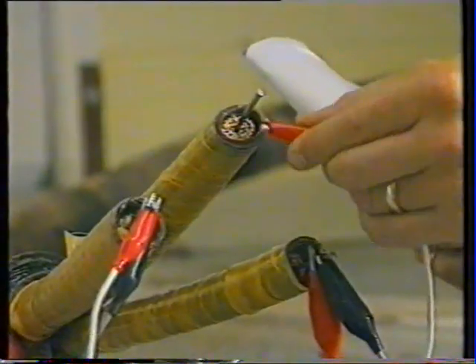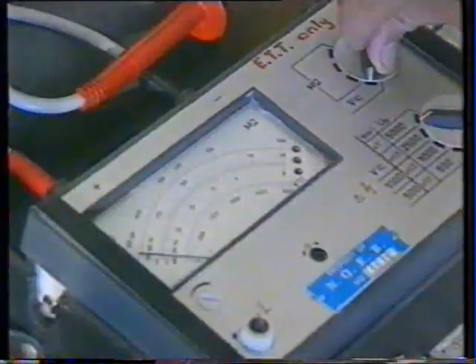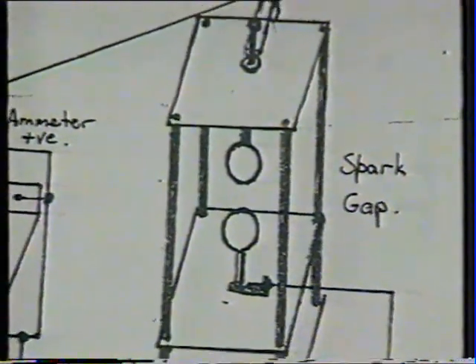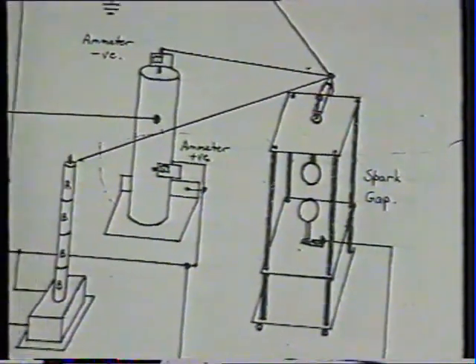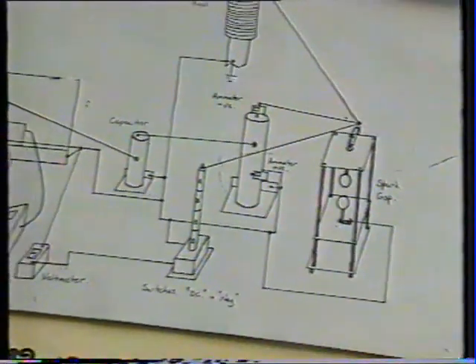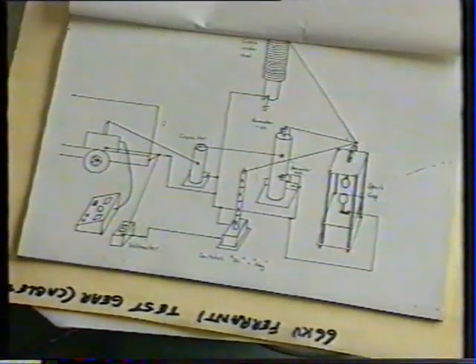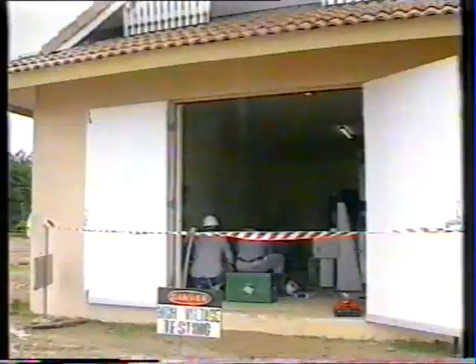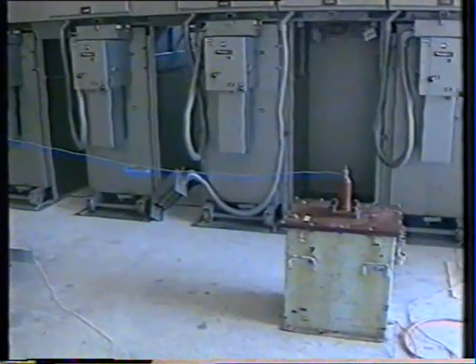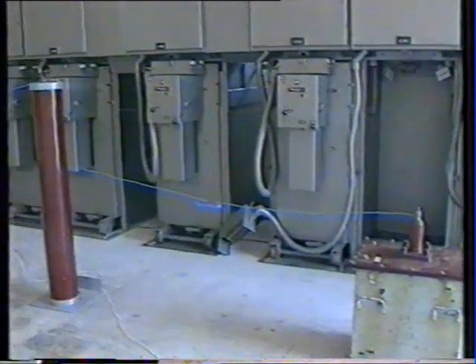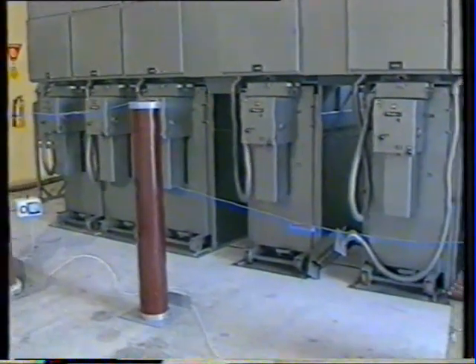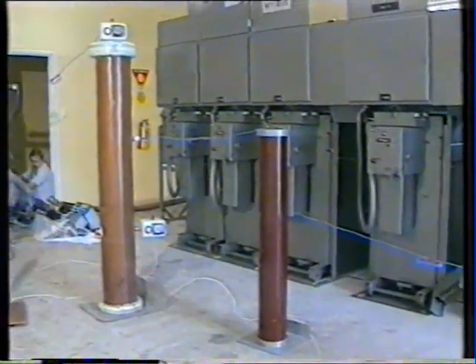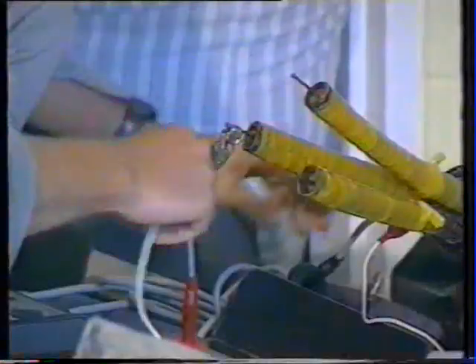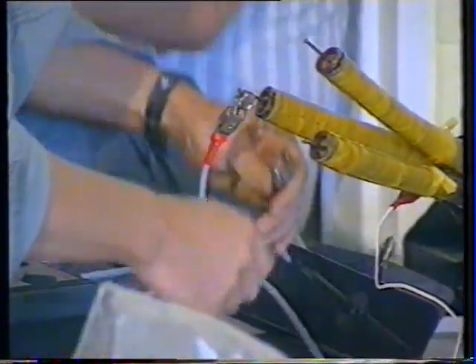This day, installation complete. The cable is ready for testing at the mainland substation. The cable is tested at 22,000 volts in accordance with the specification before termination on the 11,000 volt switchgear. Then the completed circuit, including terminations, will be retested at 11,000 volt specifications. Having met the test requirements, the cable is now ready to be put into service. Switchgear is activated and operational.